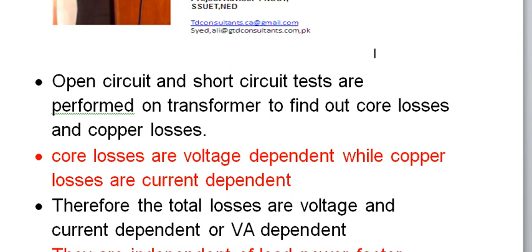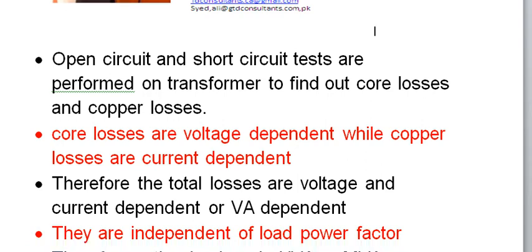So core losses are voltage dependent. For the short circuit test, we short-circuit one winding and apply voltage in such a manner that the full load current flows in the transformer. Therefore the applied voltage is very low, but the current is at full load level.